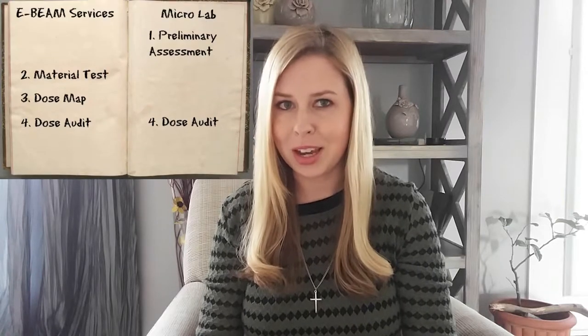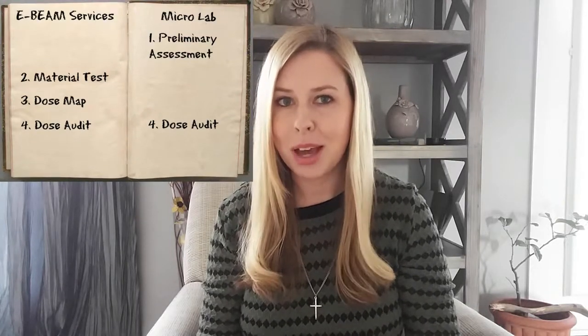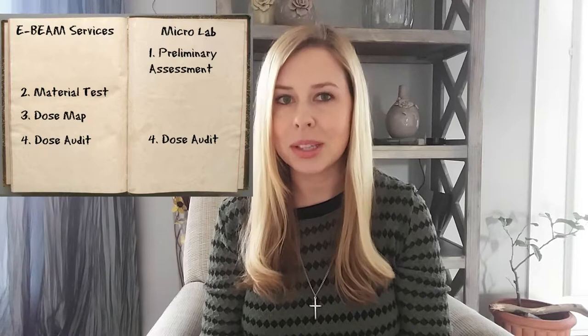The fourth and final step is a dose audit or dose verification study. Both your micro lab and your sterilization provider will help with this test, where the efficacy of the min dose established in step 1 is verified. Typically, this test is done on a quarterly basis.